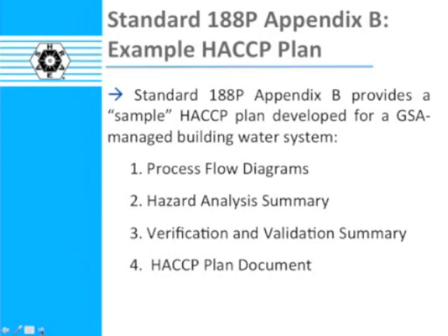And then Section 6 would further require that if that is the determination by the manager and owner of the building, that no, we don't need to do anything here because we don't have a spa, it's not a healthcare building, they go through all that list, then the standard requires that the building manager and owner reassess that once per year. Every year, make that same determination: there's no need for us to do anything more because we feel strongly that the risk of Legionella from this building is just not so.